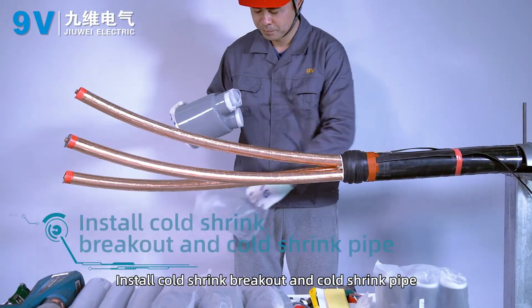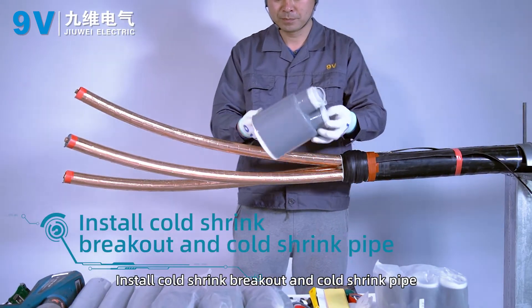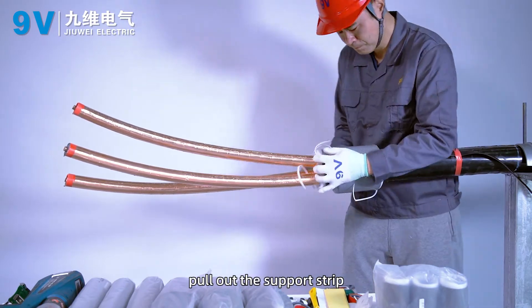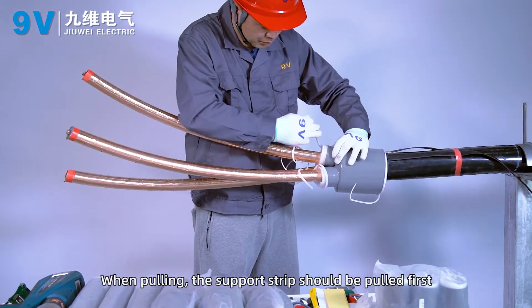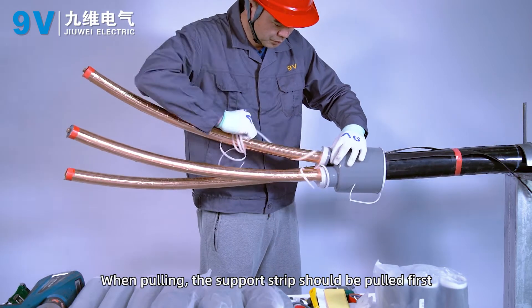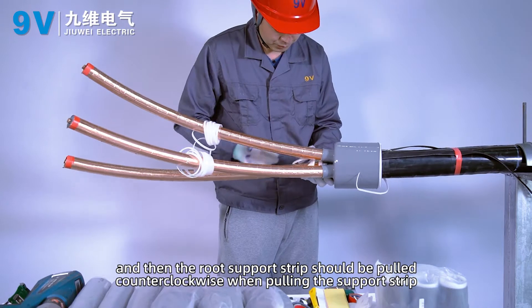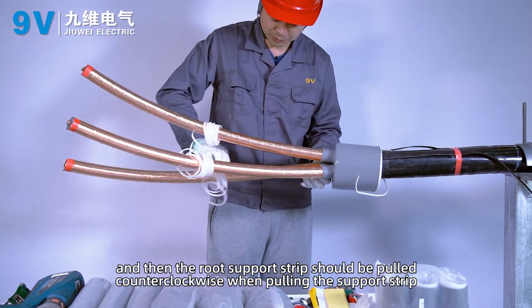Install the cold shrink breakout and cold shrink pipe. Put three cold shrinkable sleeves into the root. Pull out the support strip — when pulling, the support strip should be pulled first, then the root support strip should be pulled counterclockwise.